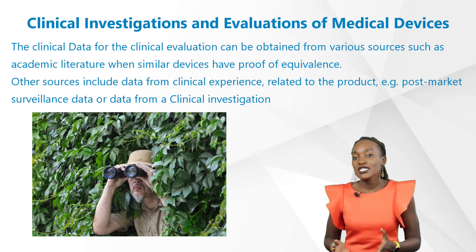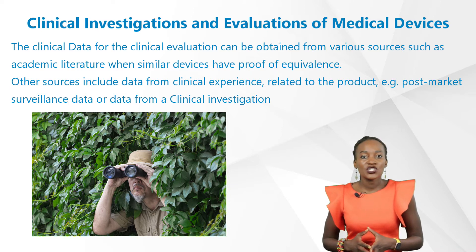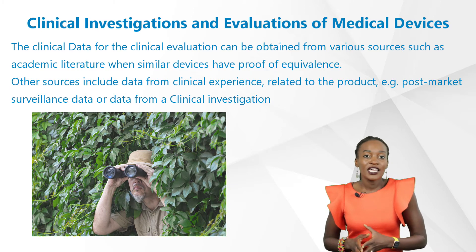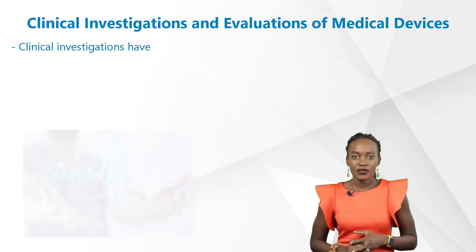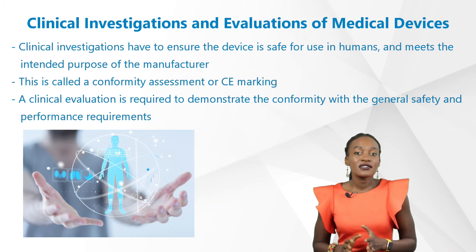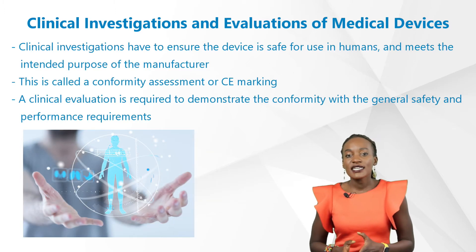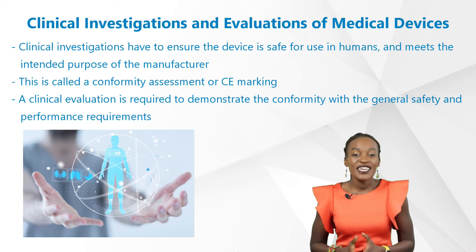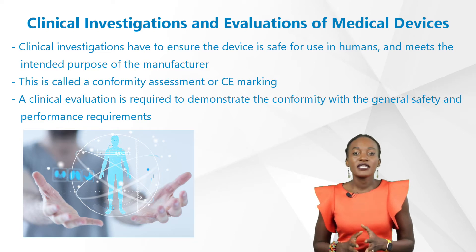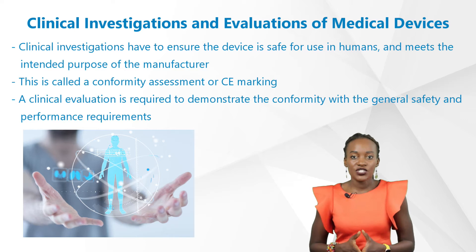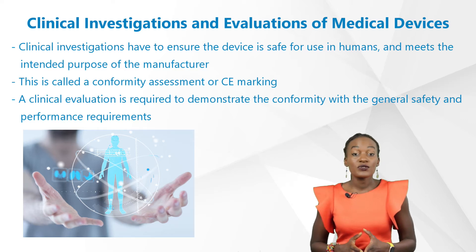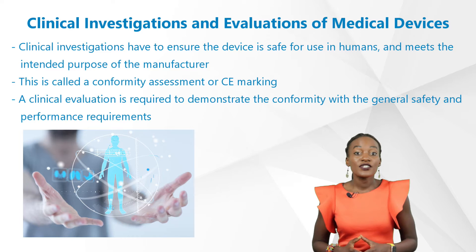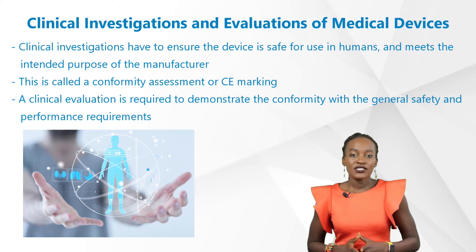Other sources of clinical data include data from clinical experience related to the product, for example post-market surveillance data, or data from a clinical investigation, as in the case of Class 3 devices and implantable devices. Similar to drug studies, clinical investigations have to ensure the device is safe for use in humans and meets the intended purpose of the device. This conformity assessment, also known as CE marking, is a topic we've also covered in a previous video.